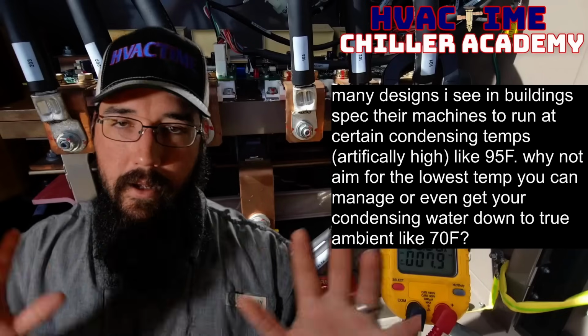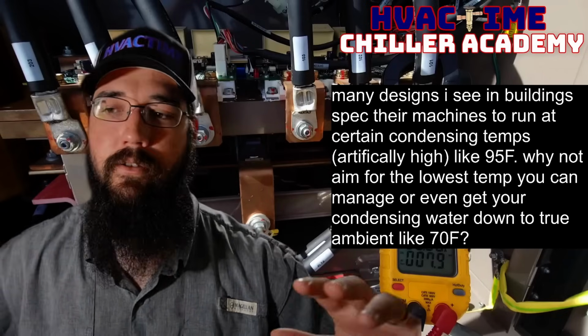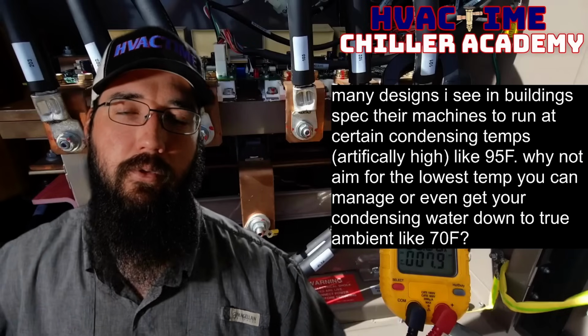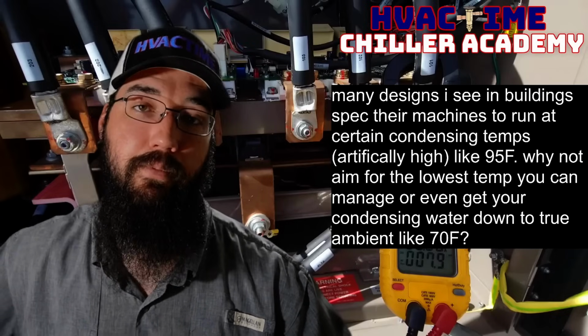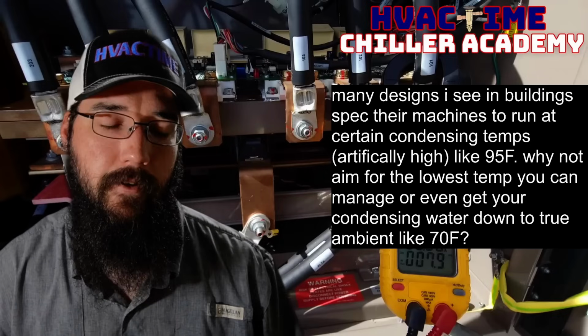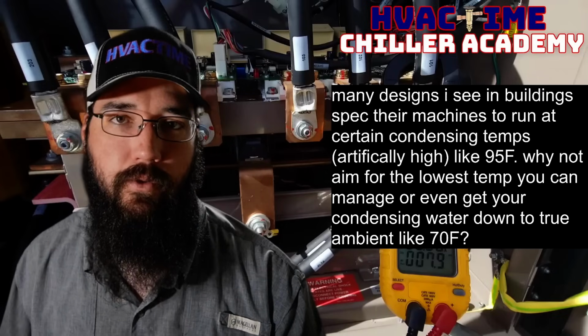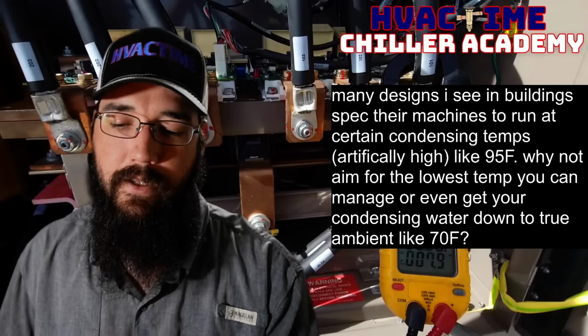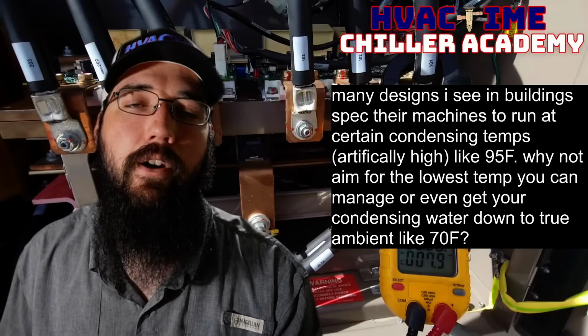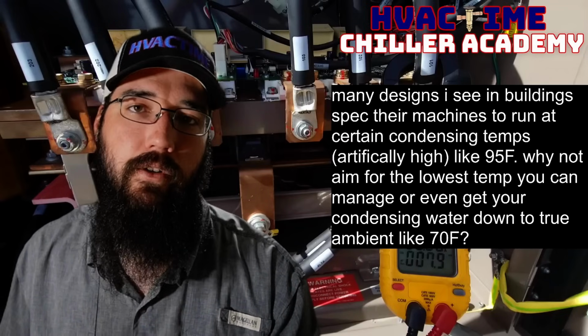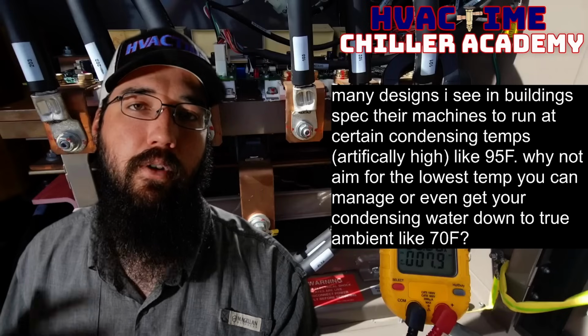So, okay, I've gone on this whole spiel about set points and not artificially raising them. It's better to put load on the tower, not the chiller. What actual solution do I recommend? Like, what is my go-to with that? Well, it is having a variable condenser water set point. To me, this is the perfect middle ground.